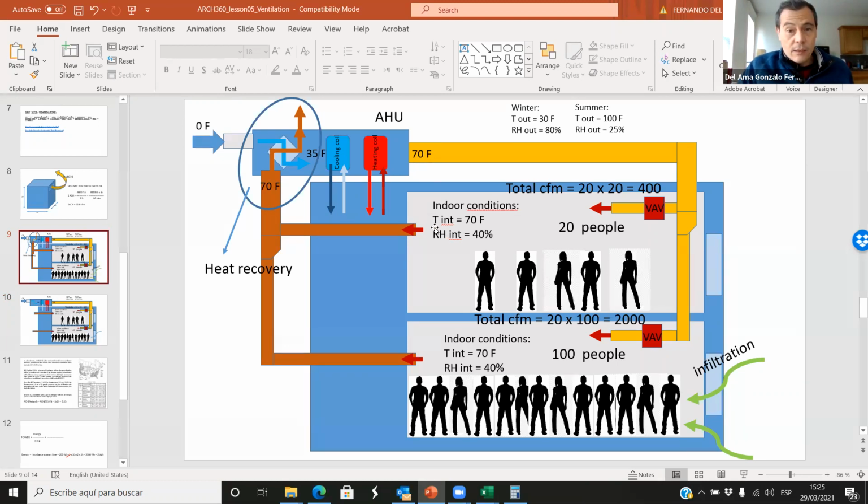I mean, the concept is very easy. Just create this ductwork, create this heat recovery, and that's fine. That's the idea, the theory. That's easy. But then when it comes to the design, we have to figure out how to avoid intersections between supply and return ducts. And sometimes if spaces are very tight, that's difficult. But it's worth it because we save 50% of the ventilation energy, and that makes sense.